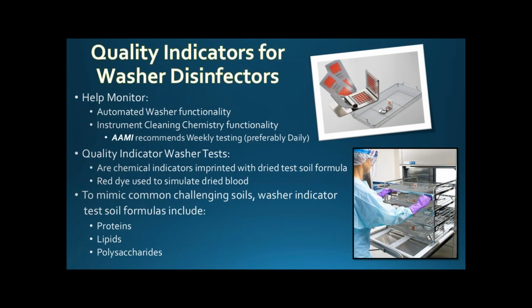With your washers, if you're using one of those automatic washers, there are quality tests that should be performed on them as well. At least daily if you're a very busy department, or at minimum weekly if you're not as busy. Each one of these is a challenge test again, so you want to make sure you're putting it on the most difficult part of your washer to clean. It basically mimics dried blood and protein and things like that, just to see if your washer is able to get all that stuff off. They should be logging this test when they do it. I know there are different types of tests, Steris has theirs, and there's another brand called a TOSI test. So just make sure they're doing a test on their washer, which a lot of people don't know, and check their logs to make sure they're doing that appropriately.